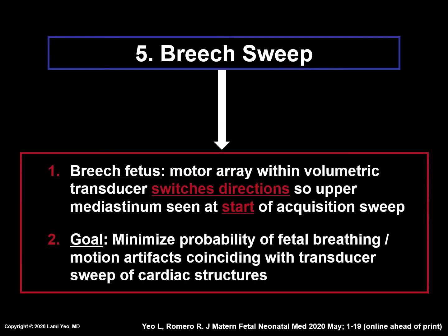Breech sweep technology is designed for breech presentations only. When there is a breech fetus, the motor array within the volumetric transducer switches directions so that the upper mediastinum is now seen at the start of the acquisition sweep. The goal is to minimize the probability of fetal breathing motion artifacts coinciding with the transducer sweep of cardiac structures.